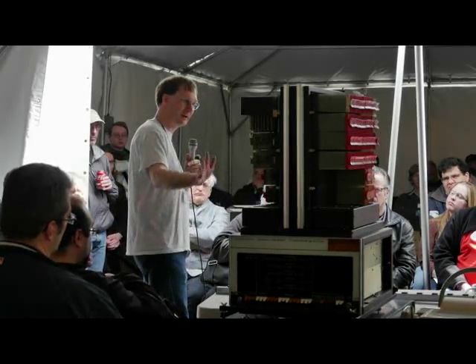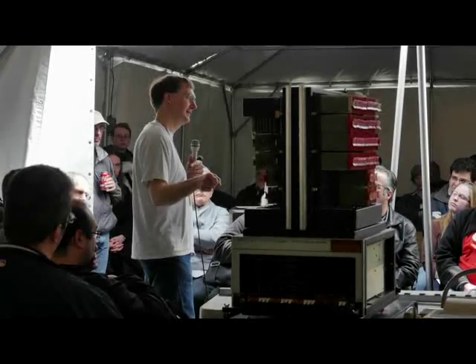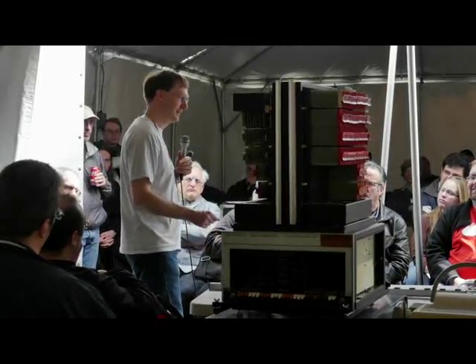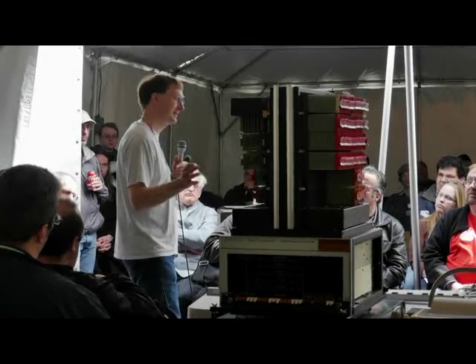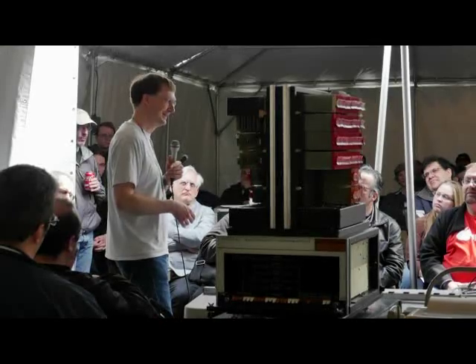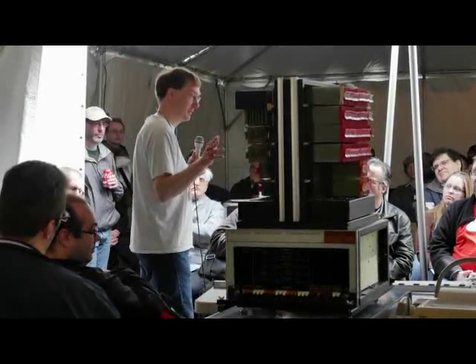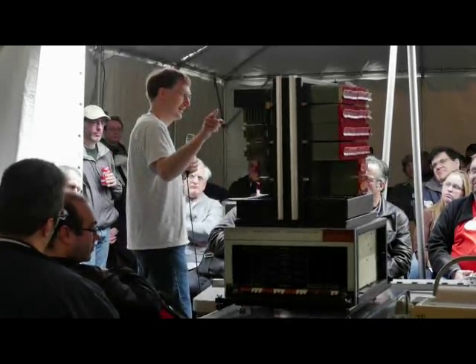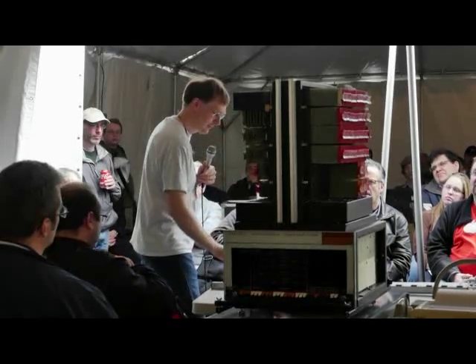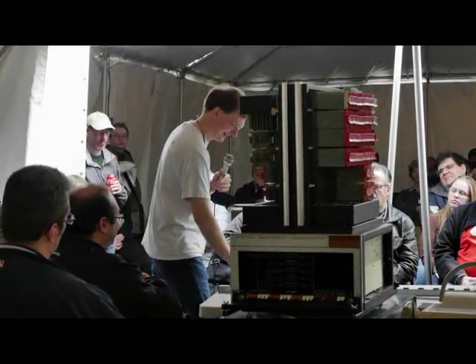And the deck also had some interesting things on AC wiring. This machine had a 10-gauge power cord and a 20-amp breaker, while the internal wiring is at best 16-gauge, going to a 7-amp switch for all the current to run through. And there's also a reasonable amount of exposed AC that you can get your hands on when these backplanes are open. So they weren't quite as big on UL codes back then, I think.